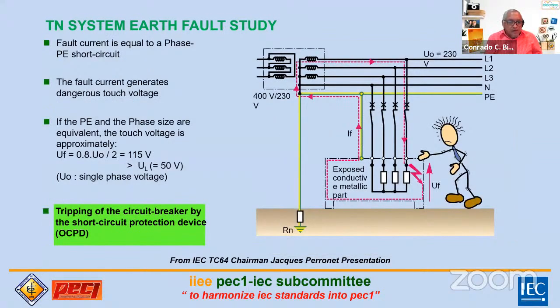Okay? Then we have the TN system. It's also a grounded system ito. And from here, dito na gumagamit ng PE, protective earth conductor. No? Continuous siya. So, meron kang fault, you must ensure na yung protective conductor mo is sized as much as possible, this is what we call sa PEC natin, effective ground fault path. Ito yung effective ground fault path na tinatawag, no? Na using the bonding conductor, okay, it will go to the source and it will trip your protective device.